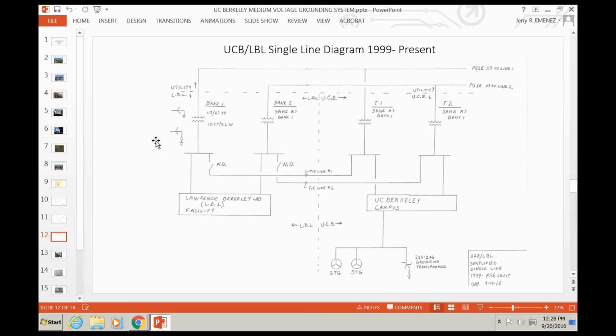kV system. They had, and they still have, some very sensitive instrumentation up there. It was their feeling that ground faults, when you have a solidly grounded 12 kV system, are very disruptive to the research instruments that are up there, both in terms of possibly damaging the instruments and also corrupting the data. So this resistor idea was really pushed by Lawrence Berkeley Lab. And again, I wasn't here when these decisions were made, but I'm told that here at UC Berkeley, we really had no problem with that because we thought it was a good idea too.